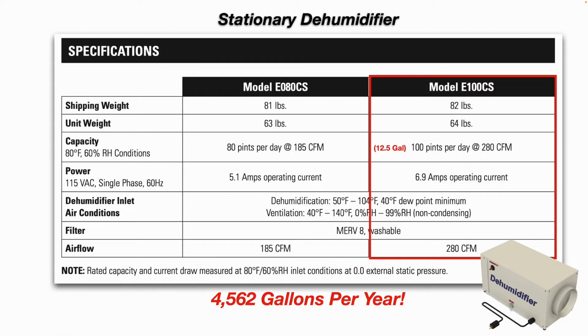They also make stationary or permanently installed dehumidifiers. That is what we're going to be talking about today on this video, specifically model E100CS. It is capable of removing 12.5 gallons or 100 pints of water out of the air at 280 CFM per day. You'll note it does draw almost 7 amps of operating current.